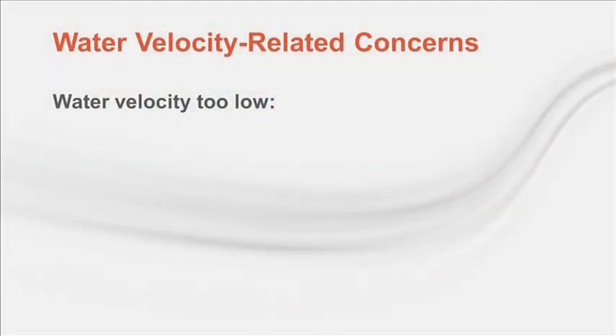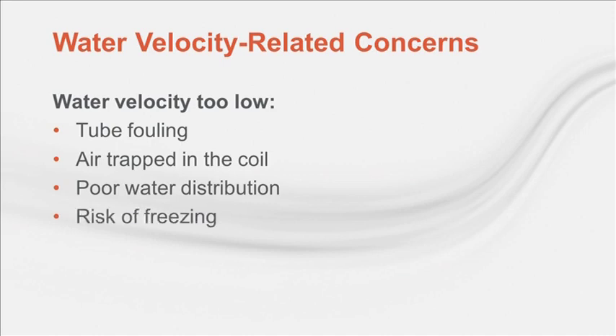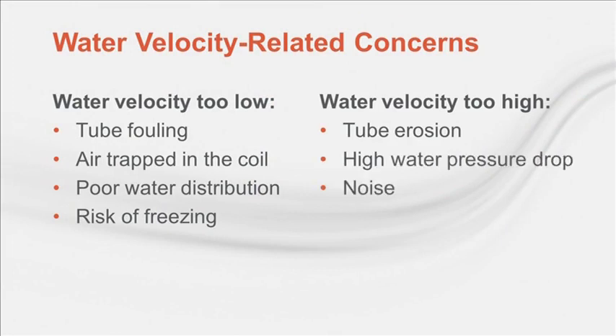Consequences of too low water velocity include tube fouling from sediment, scaling, or microbial growth; air trapped inside the tubes causing loss of capacity, noise, or vibration; poor distribution of water resulting in non-uniform coil face temperatures; and a higher risk of water freezing inside the tubes. On the other hand, too high water velocity can cause erosion of the inside surfaces of the tubes, especially at the U-bends, excessive water pressure drop, and noise. There are also diminishing returns on coil capacity with higher velocities.